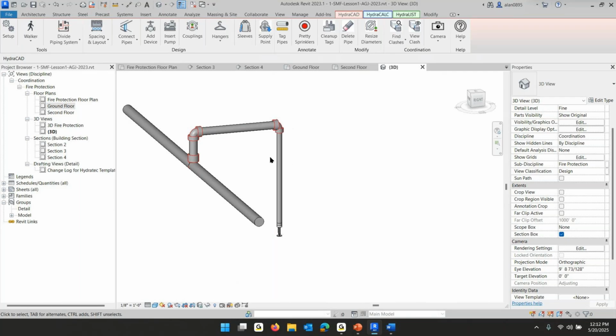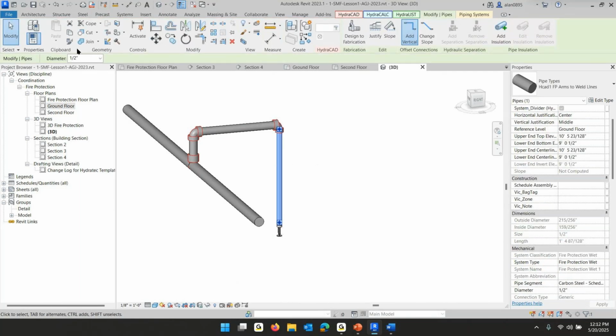This is a really skinny pipe. If I click on that pipe, I notice that it's 1/2 inch, and I would need to change it to 1 inch. It drew that pipe automatically, and Revit is just a little bit dumb. It says if I'm connecting a pipe to a sprinkler, cool, I just connect the pipe to the sprinkler. And since the sprinkler is a 1/2 inch outlet, I'll draw a 1/2 inch pipe. They didn't get the memo about needing a fitting to screw the sprinkler into. They thought you could screw the sprinkler right into a pipe.